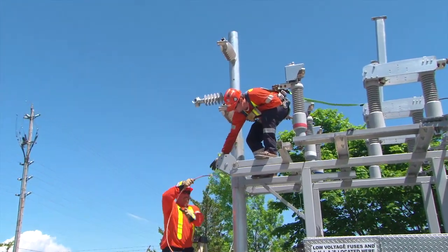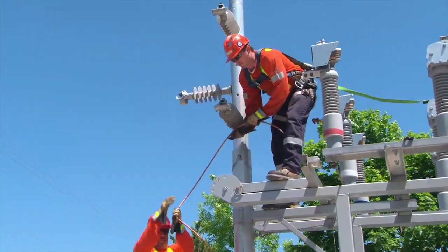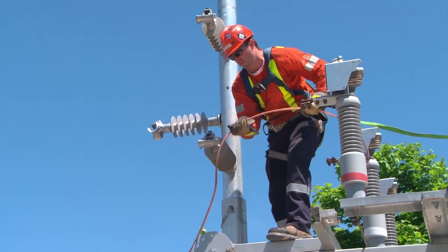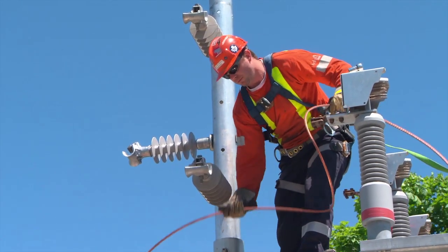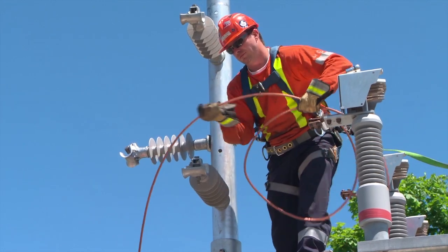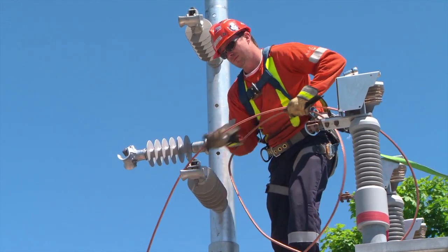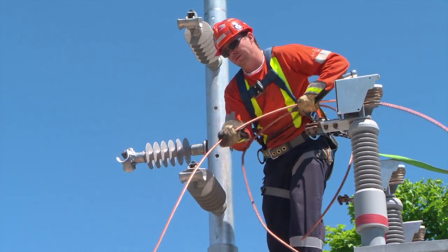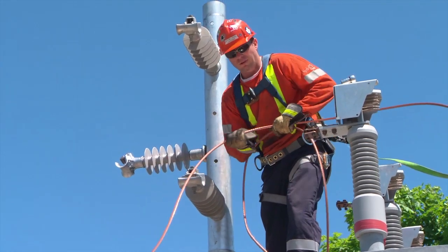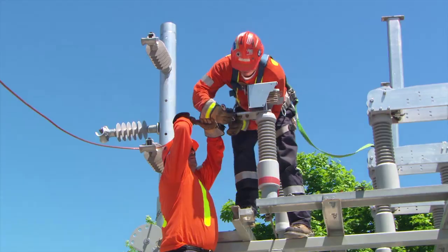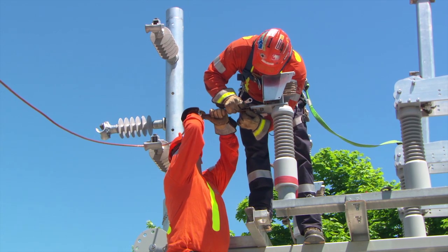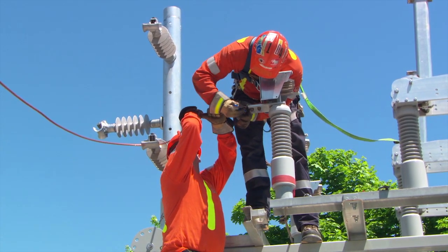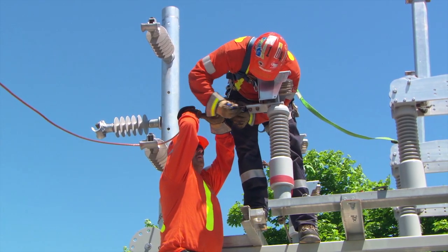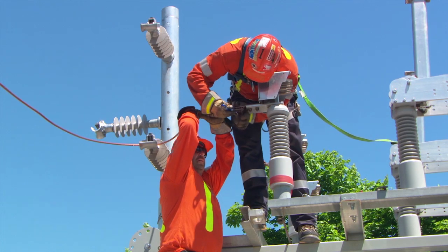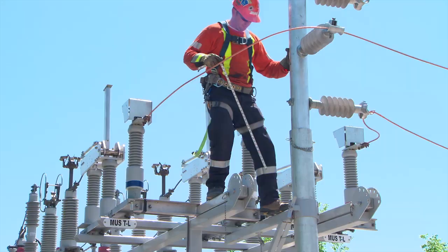Some 44 kV units are equipped with a mast, which is a vertical metal pole that attaches to the primary side of the mobile. Various insulators are installed on the mast to get the high-voltage conductors from the switch to the DS primary stirrups. A mast is required at U70 stations if bare conductor is being used for the high-voltage connections.